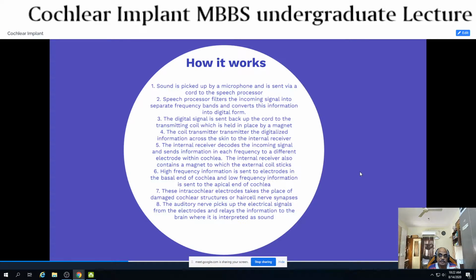So there is a magnet in the outer unit which is holding the outer unit in contact with the unit inside. We will deal with the inner component later. The outer unit and the inner unit are held together by the magnet in the outer unit and the magnet in the inner unit. So the transmitter coil transmits the digitalized information across the skin to the internal receiver. Skin is the only barrier to the transmission of impulses from the outer unit to the inner receiver.